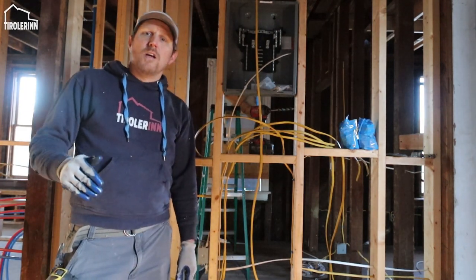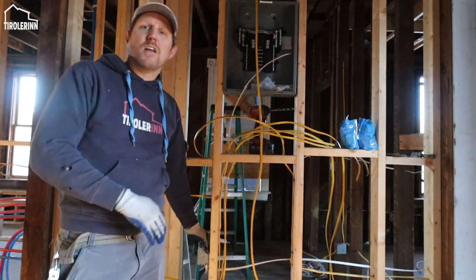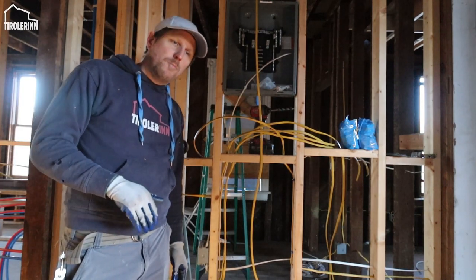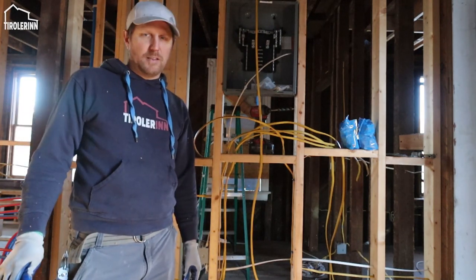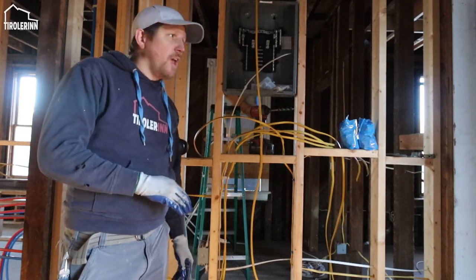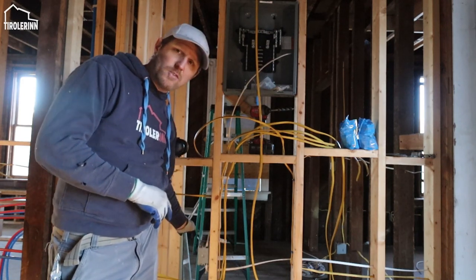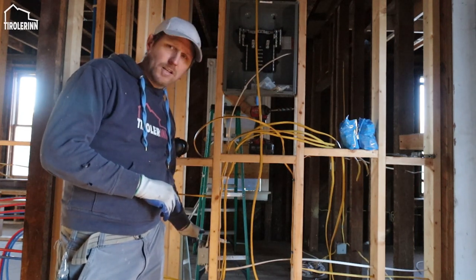So therefore, I'm putting everything onto a dedicated light circuit in the entire floor, and I'm doing it per floor. So even if the entire breaker for the entire floor falls out, I can still have lights in the rest of the house. So that's kind of the reasoning. And I always have one box, a gang box like this here. This is facing towards the closet.